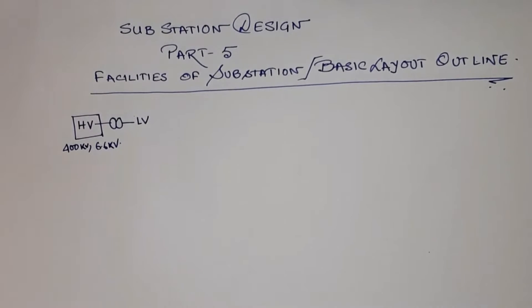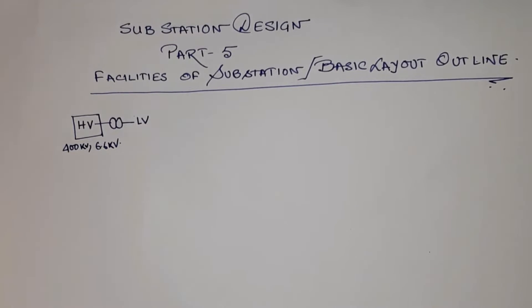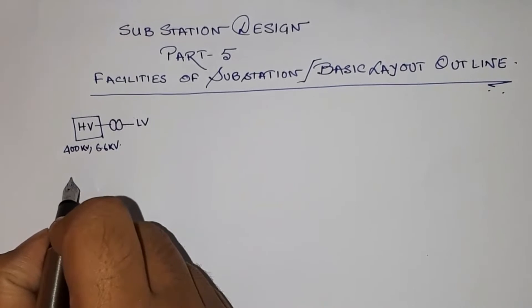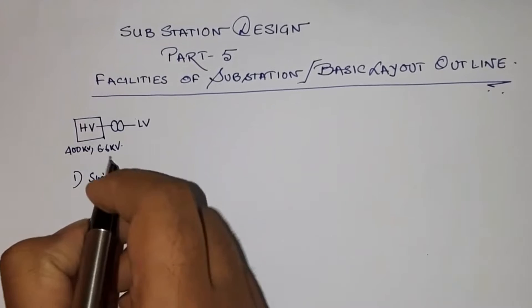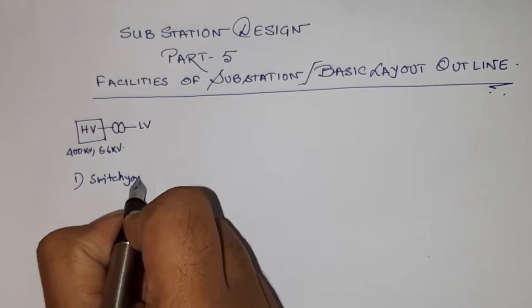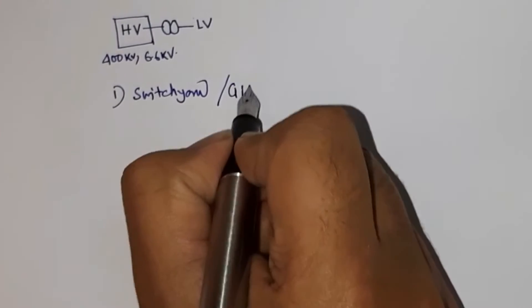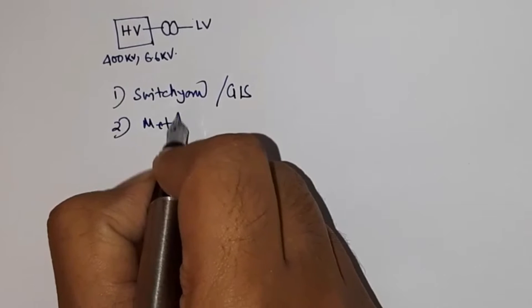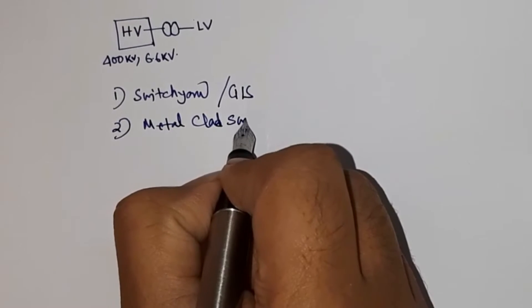As already mentioned in earlier videos, for voltage levels of 66 kV, 132 kV and above, the equipment used may be an outdoor switchyard or a GIS (Gas Insulated Switchgear). For below 33 kV, it is metal-clad switchgear which is of the indoor type. So for high voltage systems there may be an outdoor switchyard, or it could be GIS, and for MV and LV levels it shall be metal-clad switchboard or switchgear.